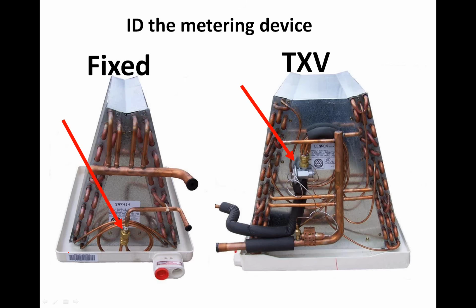And a couple things, you look at that TXV, you might notice that bulb. Well, number one, notice that the bulb is clamped down. On a thermostatic expansion valve, that bulb has to be clamped down with a copper clamp because it needs a very positive contact with the suction line. And you'll notice that that bulb is an uninsulated bulb. And the reason it's uninsulated is because it is in the airstream of the evaporator. So, the air coming off the evaporator is maybe 50 degrees, and the bulb's probably somewhere around that same temperature. So the heat gain in that part of the system to the bulb will be very, very minimal. It'll have very little influence on the bulb temperature.